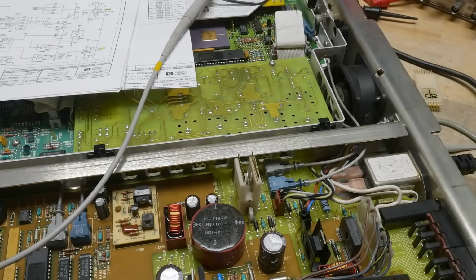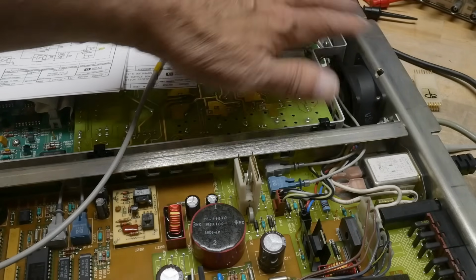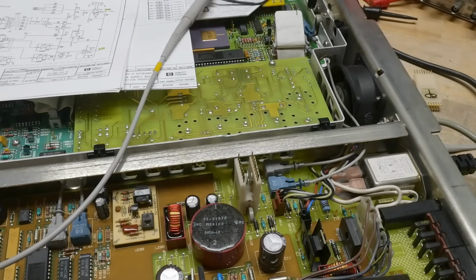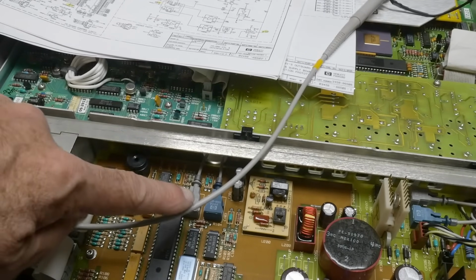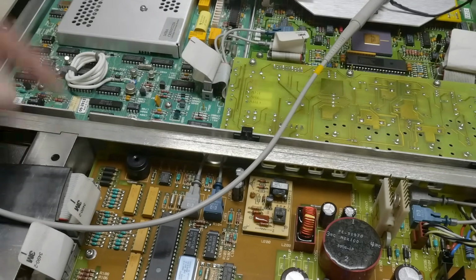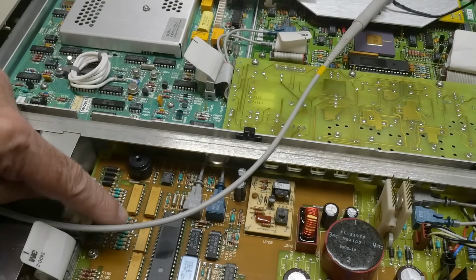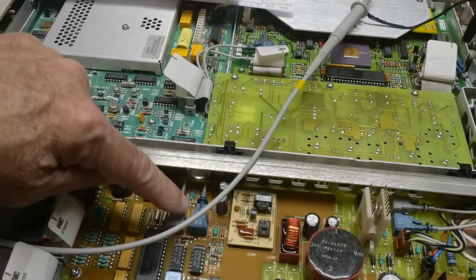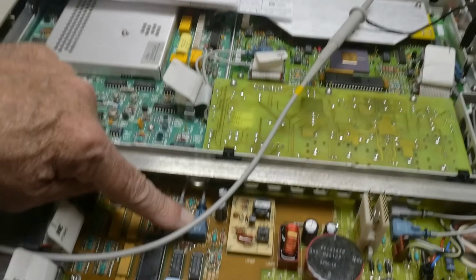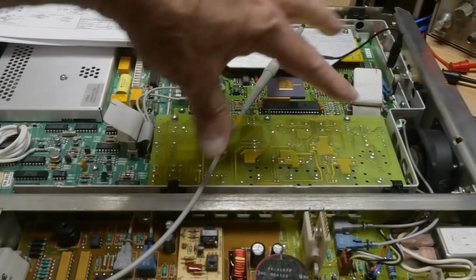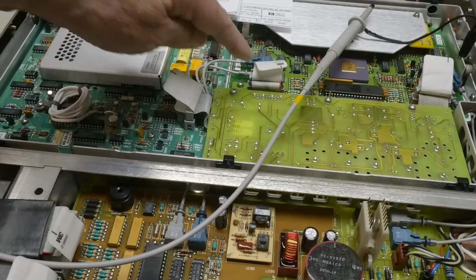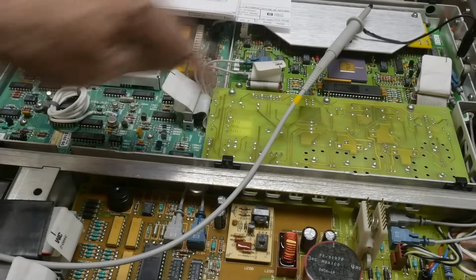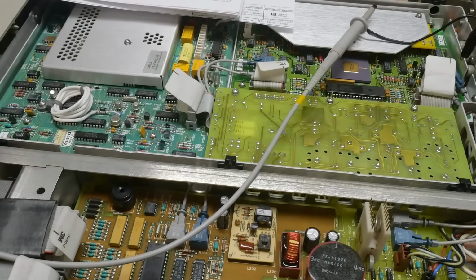So I'm really not interested in trigger in, trigger out. So that's what this whole thing is here. What I'm interested in is data in, data out, and that is over here. Okay, so this is our microprocessor for the front panel. Here's the data transmit receive, and it comes from here, which is the A to D board. So we want to see if this path is working correctly.